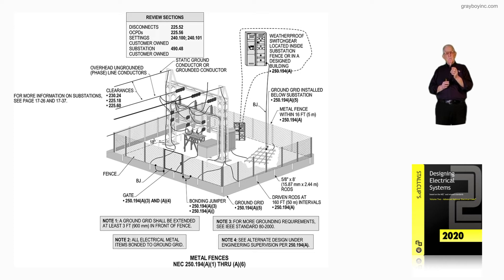More additional information is recommended on pages 17-26 and 17-37 in Volume 2 of Stallcup's Electrical Design book. Our bonding jumpers would have to meet 250.194A(3) and 250.194A(4). You have your ground grid and your driven rods that are driven down at intervals not to exceed 160 feet in accordance with 250.194A.